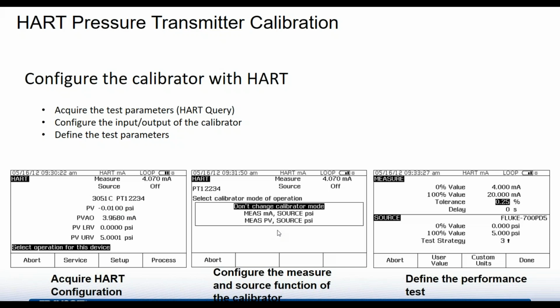From that point, now you want to configure how you're going to measure and source. In this case, you'd be sourcing your pressure and measuring your milliamp value. Finally, you want to define how you're going to do the test. In this case, we're going to set up our tolerance, and that's the accuracy required by the customer, and that's of course determined by what your company requires for your standards. And then lastly, you've got your 0 to 100% values, which are automatically read by HART, but you want to put in what kind of test strategy you want to do in the calibration. For example, in this case, it's set for a 3-up, so you'd go 0, 50%, 100% of that 0 to 5 psi.